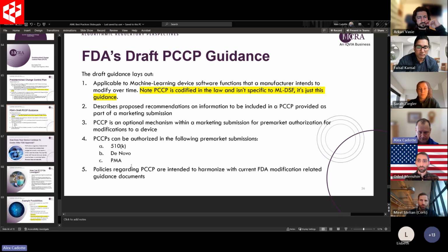What I've seen people do is have like a 3-page PCCP they toss into their 510K, and FDA will give them like 20 or 30 deficiencies related to it, just because it tends to be more of an activity that's more like 50 to 100 pages worth of documentation. So the level of specificity, the level of documentation that FDA is asking for is pretty high. So in the end, the main thing for a predetermined change control plan for any of these mechanisms, the first thing you should be doing is determining whether it's worth it.